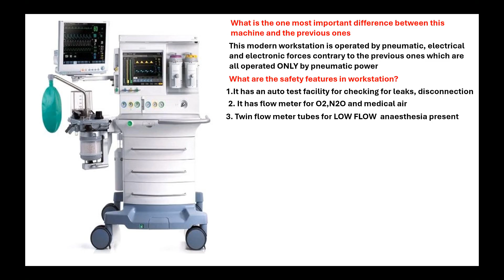100 ml to 1 liter maximum. So that you can give very low flow like 200 ml, 300 ml also can be given. Earlier the lowest was 100, now they have even reduced it to 50 ml, and the maximum that can be delivered by the first tube if the bobbin is raised up is 1 liter. Whereas the second tube will deliver from 1 liter to 10 or 15 liters. That is how the tube is designed for low flow anesthesia to prevent theater pollution as well as cost, economy, everything. And there is a hypoxic guard to prevent hypoxic mixture.